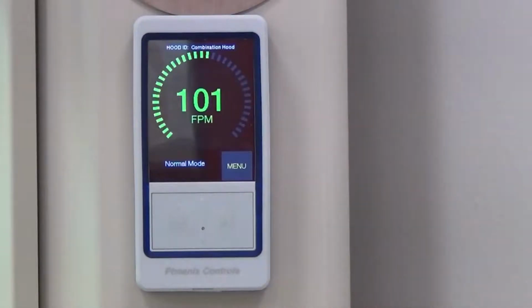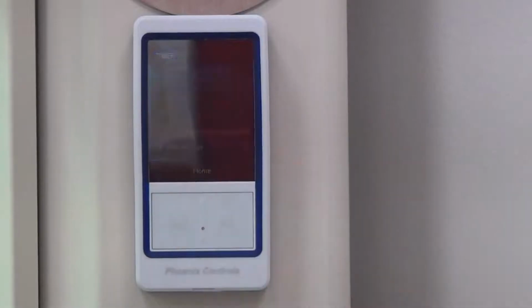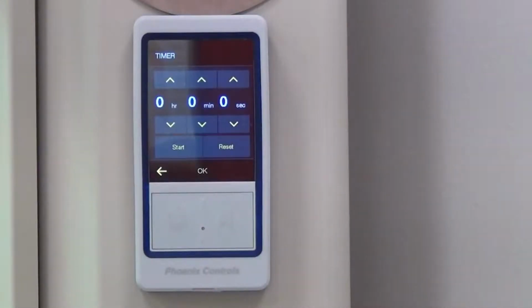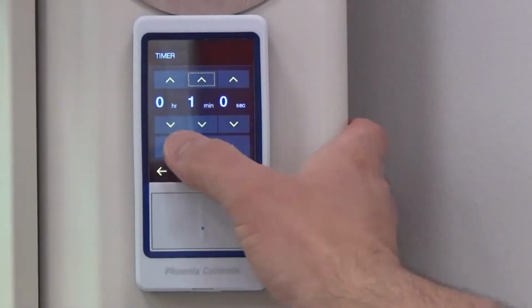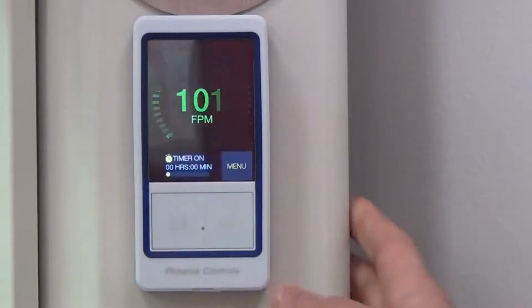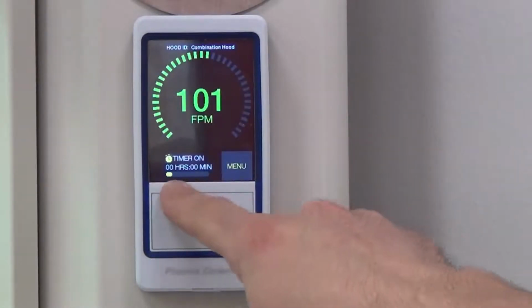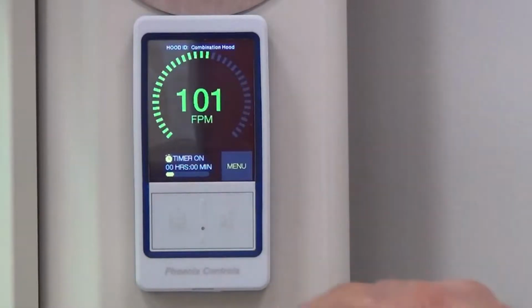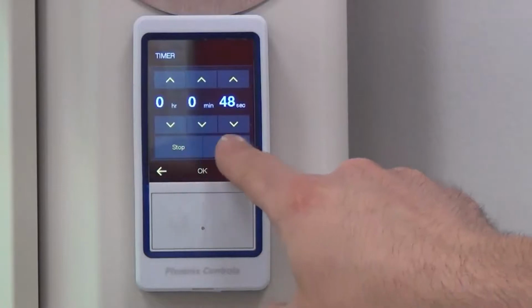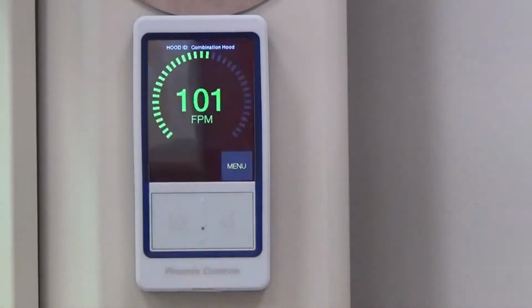The other feature that we added to this that's a real nice to have for an end use customer is the fact that we added a stopwatch timer in here. So a lot of times we would see these kitchen egg timers on the fume hood below the fume hood monitor where people would want to be timing a reaction. It beeps and they know they need to go check their fume hood. So realizing that people use that on a day-to-day basis, we decided to put that functionality into our fume hood display. So we have the ability to put a timer on here. You can hit start and go back out to your main screen, and it'll actually show the timer running right here. It'll have this little yellow bar will count down. When it's done, it'll actually show timer done. For now, I'm just going to go ahead and clear that. But again, that's another feature that we added to this to make it a little bit more user-friendly.